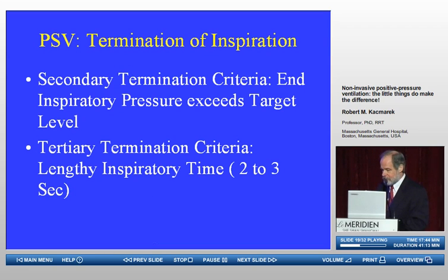And if I can go to the next slide, forcing exhalation to occur by cycling with the secondary criterion, which is an increase in airway pressure, after so many milliseconds into the breath, of a certain number of centimeters of water. And every ventilator uses a different algorithm to figure that out. But every single ventilator on the market that allows pressure support as a mode of ventilation has an excess pressure at the end of the breath as a secondary cycling mechanism. And that's what you'll see happening frequently in these types of patients.